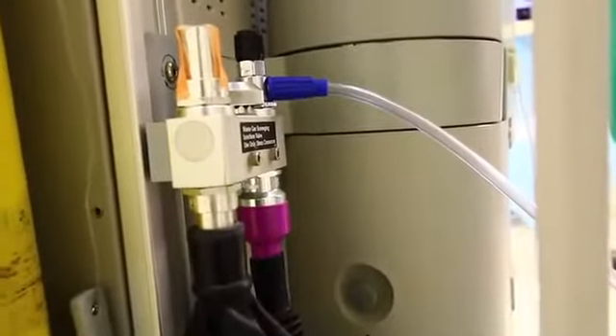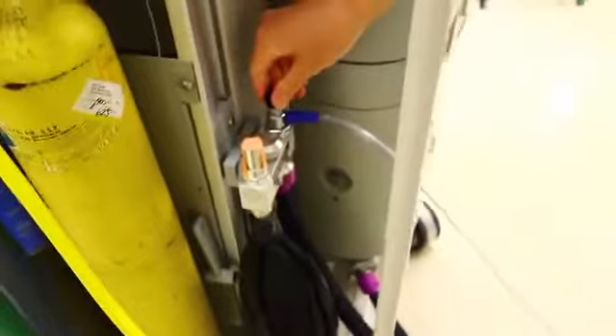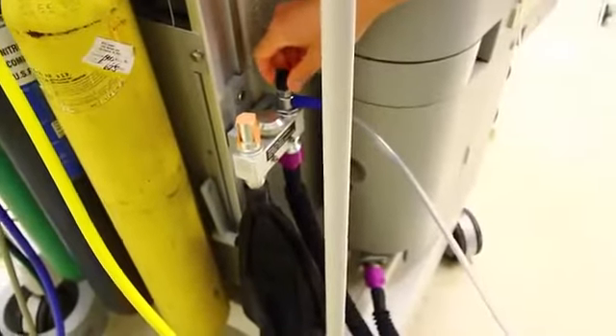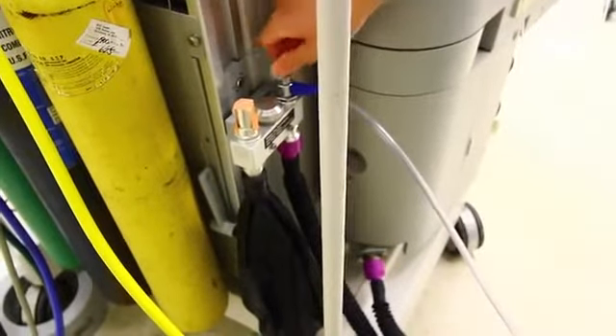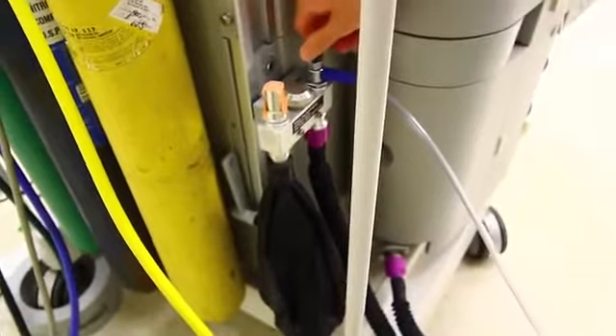Now check and adjust the scavenging system. Ensure proper connections and adjust the waste gas vacuum. Turning the knob counterclockwise increases the suction and vice versa.